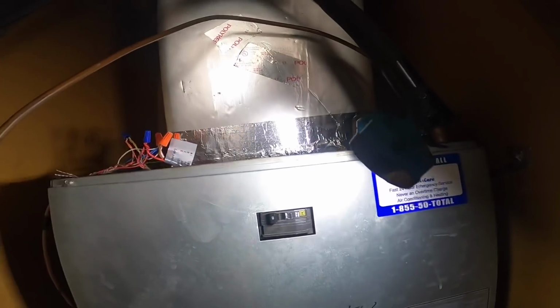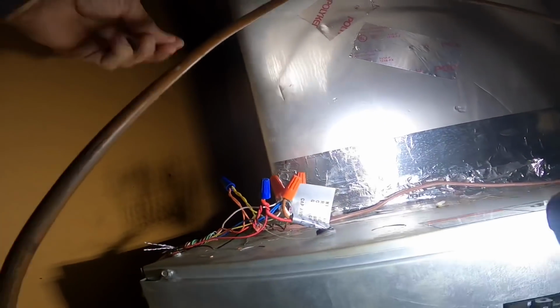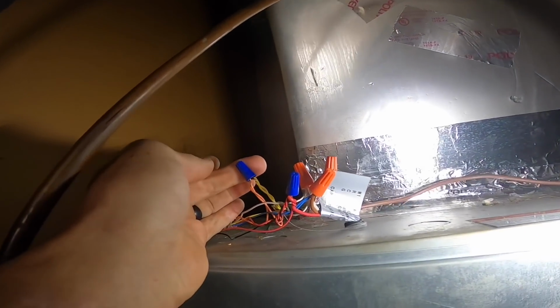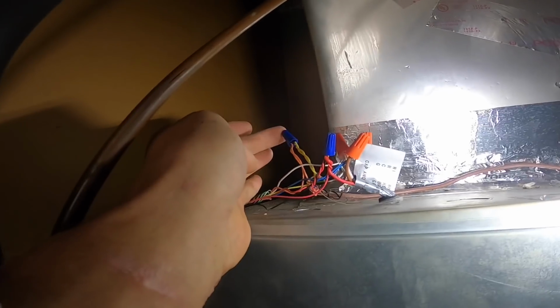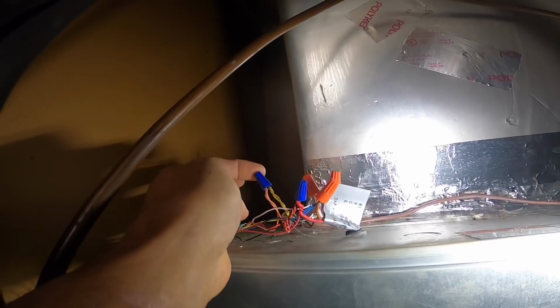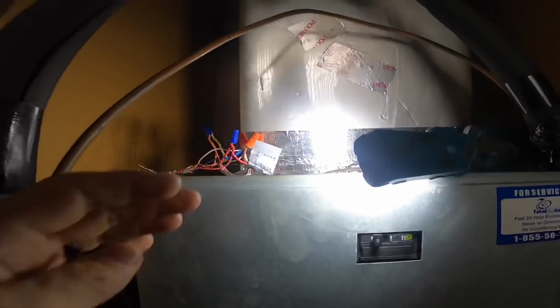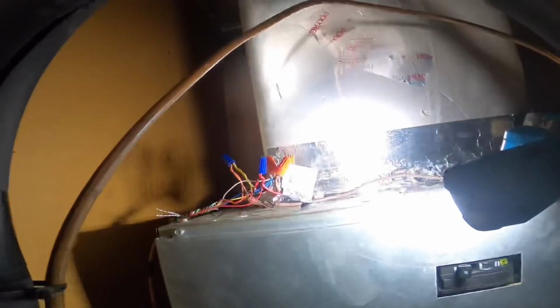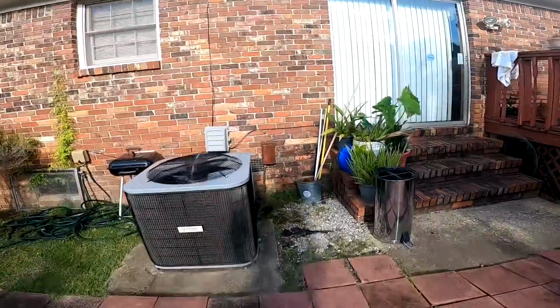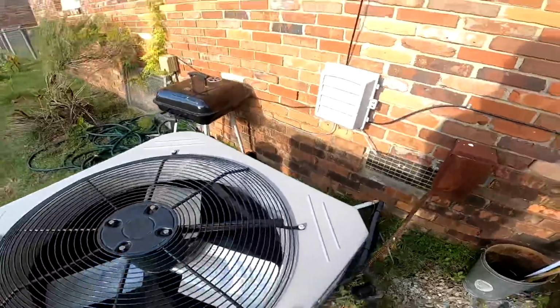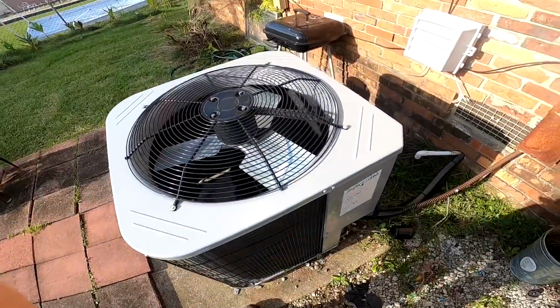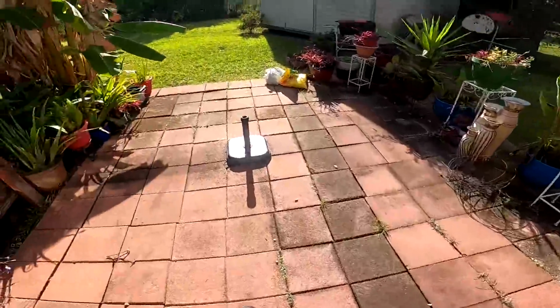All right, on this one, the customer said it's blowing cold air. First thing I see is orange and yellow are tied together. That tells me we probably got a heat pump and somebody has rigged this up to run in just cool. So I'm gonna take a trip outside and see what we got. All right, we have an ICP with a reversing valve down there. So I'm guessing they got the wrong thermostat or something and just kind of rigged it up.